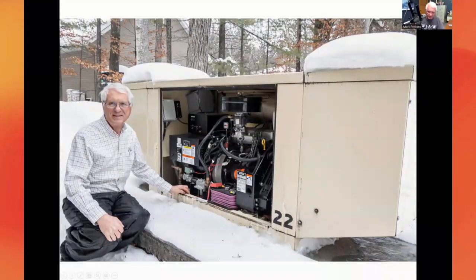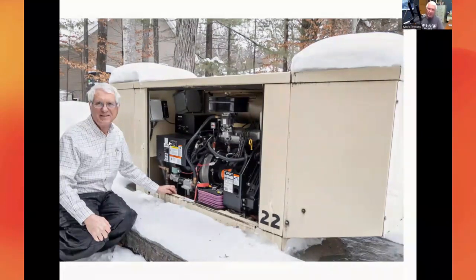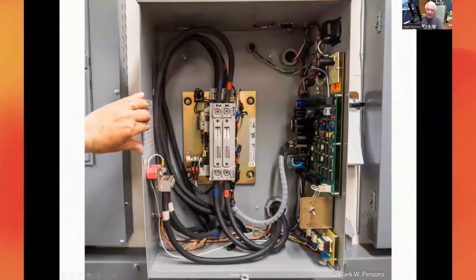And it's all self-contained. It's just terrific, and it works great. And Kohler puts these marvelous controls on that control the speed. Well, what's important about the speed? Speed means 60 hertz, not 59 or 75, but 60 hertz. Here's the transfer panel that makes that generator come online. On the right is a circuit card that looks at incoming city power, and it waits to see if the power loss lasts a full 5 seconds. And if it does, at that point, it then sends a signal to start the generator.